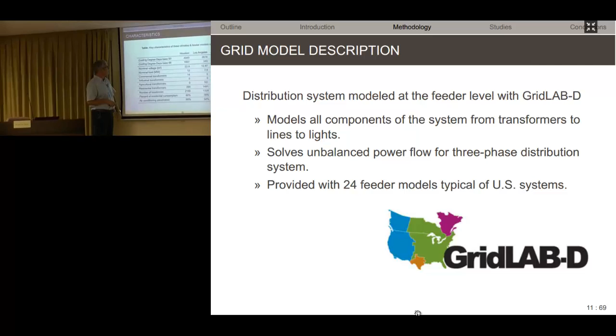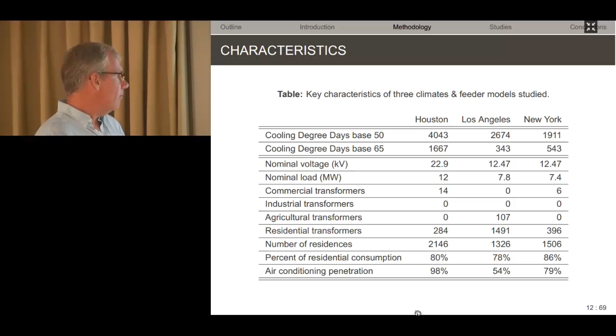And let's just look at Houston for right now. This is a 22.9 kV feeder with 12 megawatts of nominal load, 14 transformers connected to it, 284 residential transformers, and that serves a total of 2,146 homes. And 80% of that load is residential. So 80% of the total consumption on the feeder is residential, and 98% of the homes have air conditioning in Houston. Right? Who's ever been in Houston knows that's a necessity.